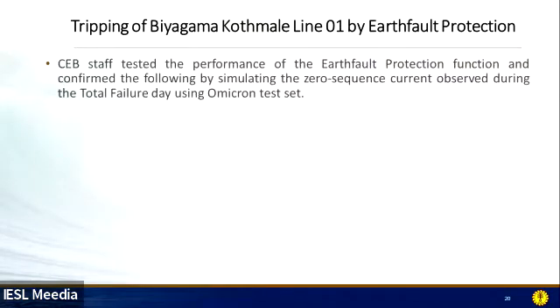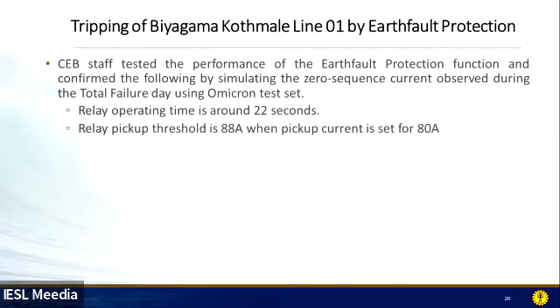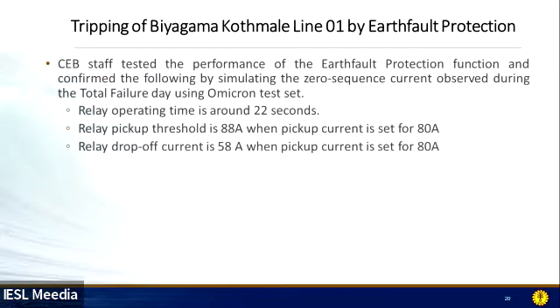After that, CEB staff tested the performance of the earth fault protection function, simulating the zero sequence current observed on the total failure day using the Omicron test set. The relay operating time is around 22 seconds. The relay pickup threshold is 88 ampere when the pickup current is set for 80 amperes. The relay drop-off current is 58 ampere when the pickup current is set for 80 amperes. That is what we observed theoretically, and we proved it by injecting current into this particular relay model.